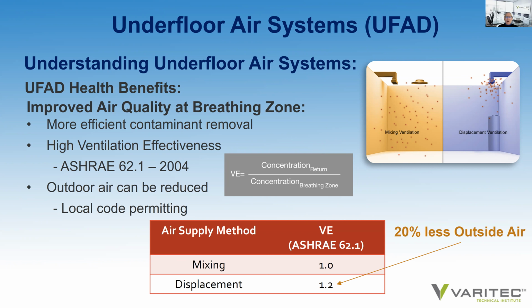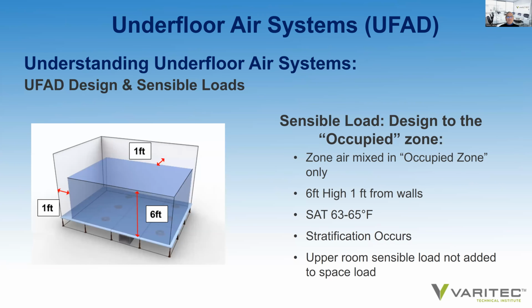Well, why is that? Why is air quality better at the breathing zone? If you look at the graphic to the upper right, it demonstrates how a mixed air system is doing its job if it uniformly dissipates contaminants and pathogens throughout the cubic volume of space. However, in a displacement ventilation system or a UFAD system, because of the convective plumes, contaminants and viruses tend to drift upward into the upper levels of the room where the exhaust grills are, so you have a higher concentration of contaminants in the upper level of the room where they're evacuated, exhausted from the space.